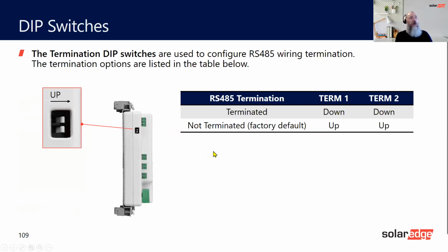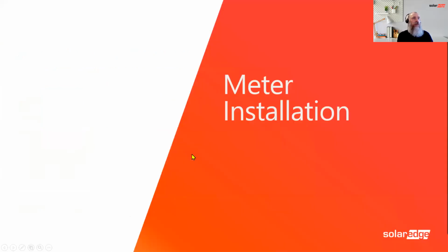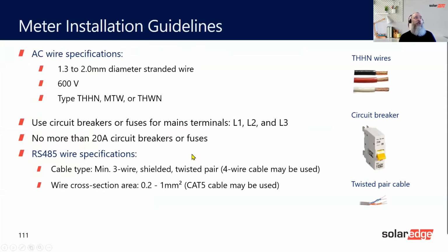This is the end of line, not terminated, factory default. So terminate 1 and terminate 2. Okay, the dip switches are here for the RS485. So installing the meter, you don't need to have a 20 amp MCB. You can have smaller than that. It really doesn't take much power to actually energize this.